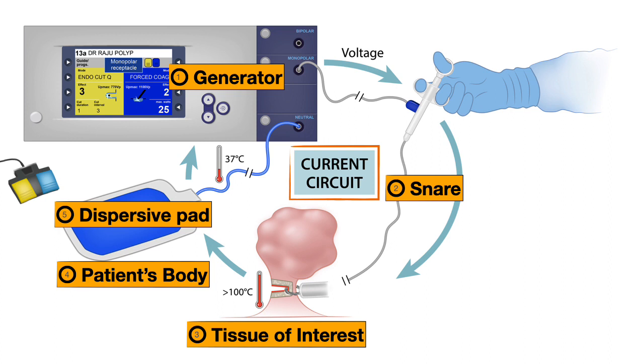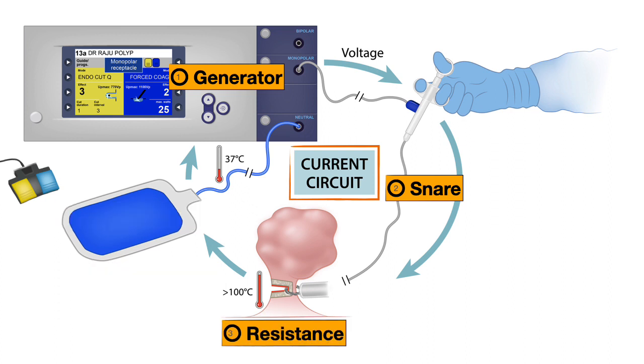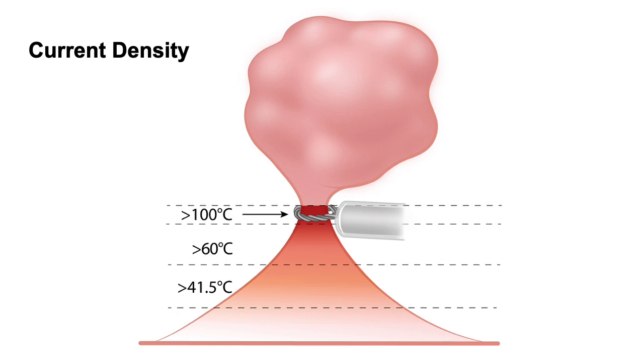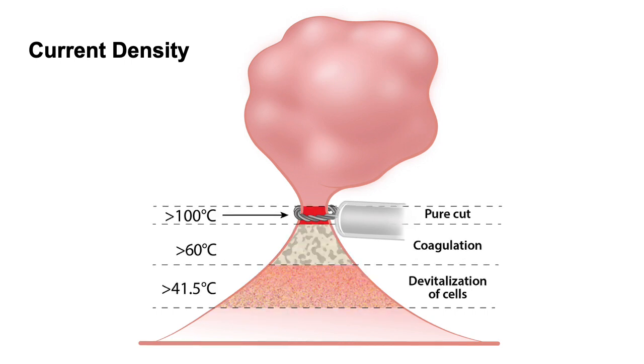What happens when you use this type of circuit? The current goes from the generator to the snare to the tissue of interest, and then the local temperature increases to above 100 degrees if you're planning to cut, and that intense heat is the one that delivers the desired effect. And at this point, I would like to introduce a concept that is important for all of us to keep in mind, that is current density. So take, for example, a pedunculated polyp, and you put the snare around the stalk of the polyp and you squeeze it, and wherever you squeeze it, that's where the current density is the maximum, and that's where you get the maximum heat, and that's where you will see the cut.